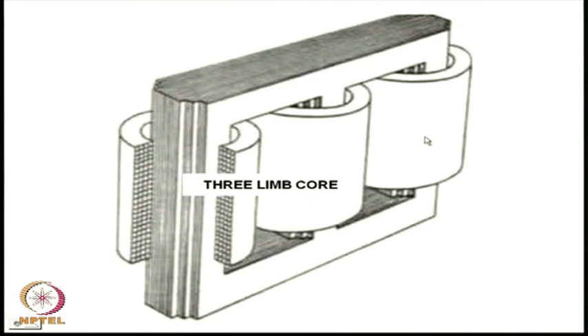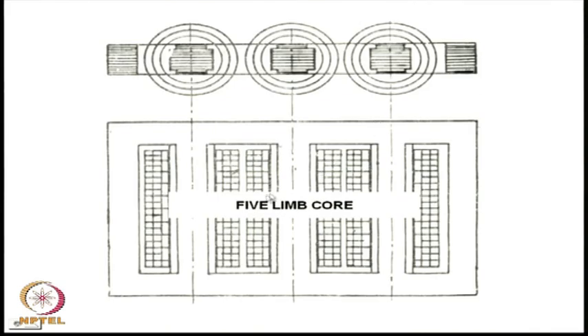In the last lecture we have seen that a three-phase transformer built as a single unit can be made up of three limbs. The return limb for the flux is not necessary, since the sum of the fluxes is 0. However, this three limb construction does offer slight imbalance to the flux path. Therefore, for very large transformers a 5 limb construction is used, where the windings are placed on the inner limbs, and the two outer limbs do not carry any winding. This provides a more balanced magnetic path for the three phase flux, and the phases operate more or less independently of each other under balanced operating conditions.